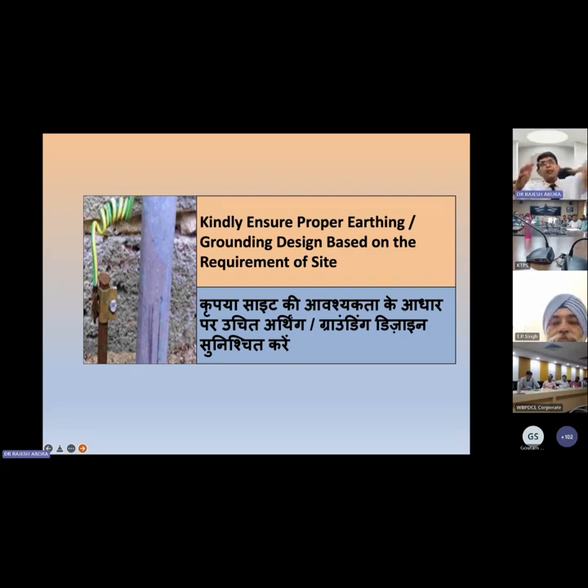It should not be that there is separate earthing for your electronic system, another electrode for your power, and another for your lightning. All must be interconnected and you have to go for global earthing. IS 3043 definition, page number one, starts with the global earthing concept. It clearly indicates that all the earthing systems in a particular location, the particular premises, must be interconnected. The same thing has been depicted in IS 732 also. IS 3043 also talks about interconnection of your lightning and power earthing. Don't get confused. Just keep in mind OLOE: one location, one earthing. Your problem will be over.